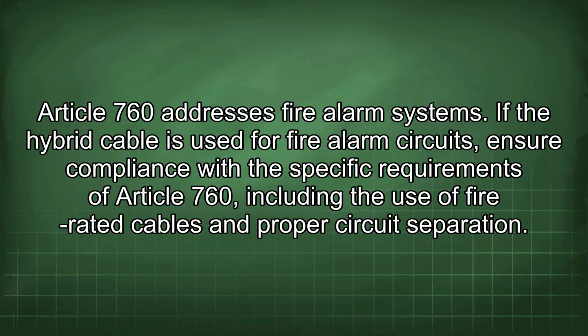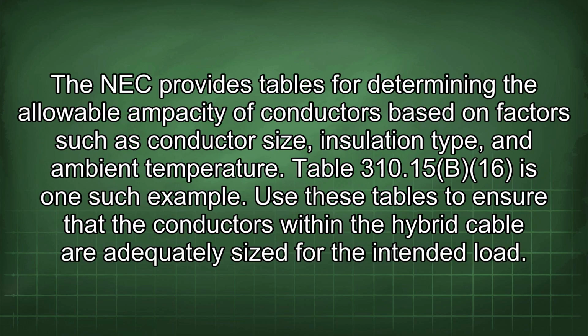Article 760 addresses fire alarm systems. If the hybrid cable is used for fire alarm circuits, ensure compliance with the specific requirements of Article 760, including the use of fire-rated cables and proper circuit separation. The NEC provides tables for determining the allowable ampacity of conductors based on factors such as conductor size, insulation type, and ambient temperature. Table 310.15(B)(16) is one such example. Use these tables to ensure that the conductors within the hybrid cable are adequately sized for the intended load.